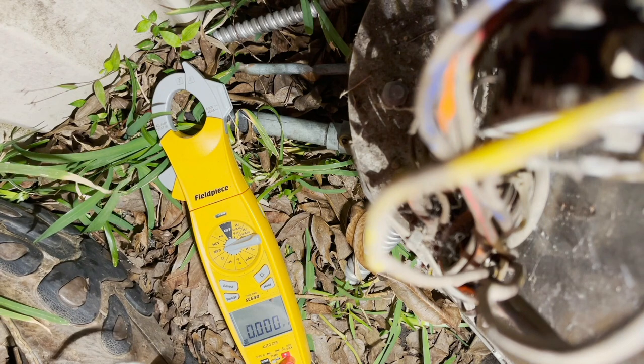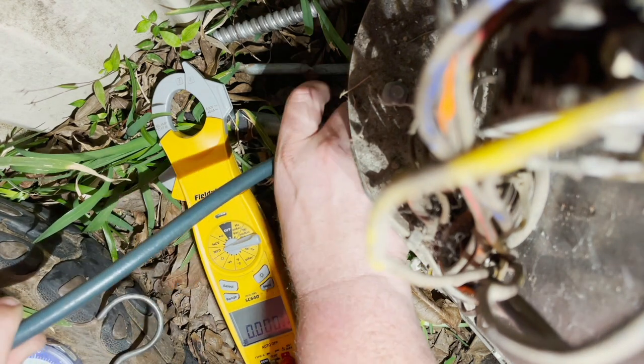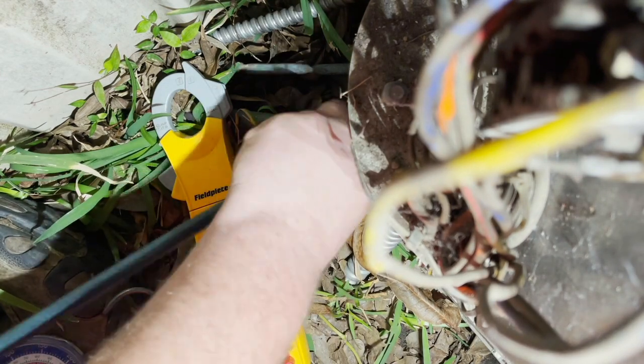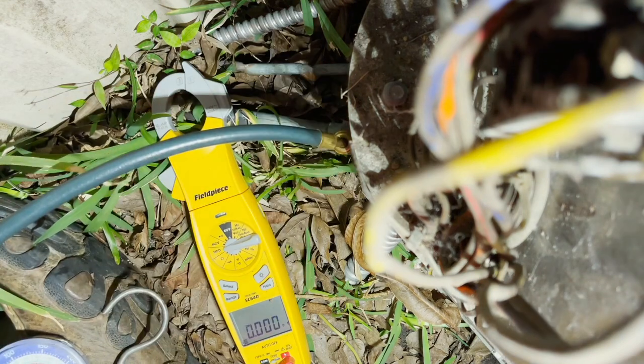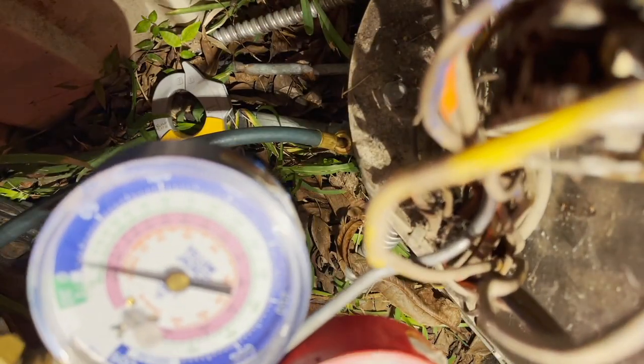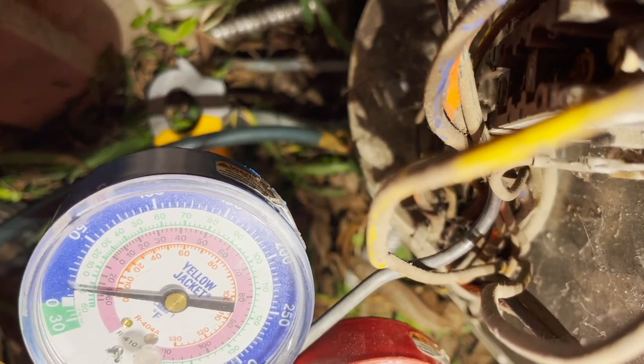I can't really check it properly but I want to check the standing pressure, and I believe this thing doesn't have much gas in it. Sure enough — it has about 15 to 16 pounds of pressure. The system is just not worth fooling with; it needs to be replaced, and that's what I'm going to give a quote on.